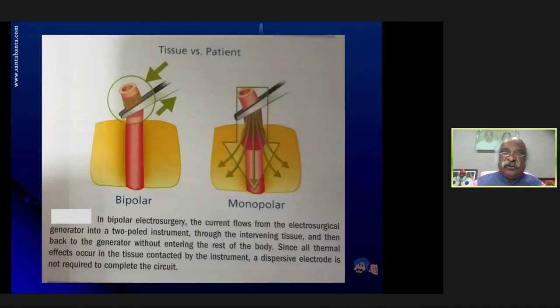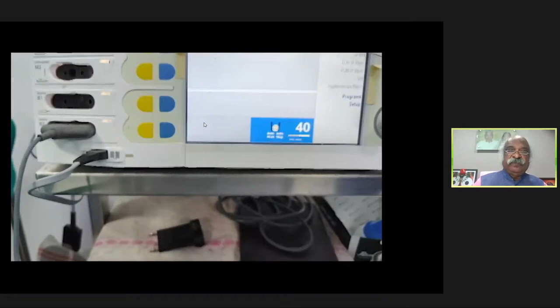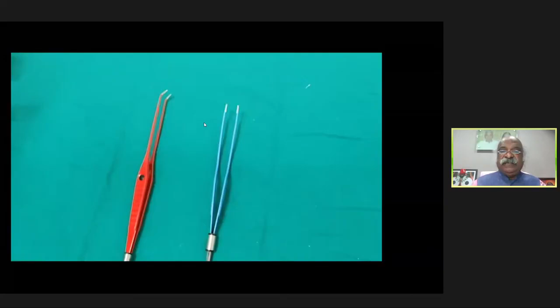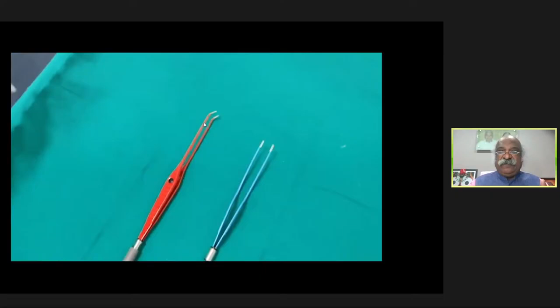Whereas in the monopolar, what happens? It goes through the electrode and directly through the tissues, and then it passes through the dispersive electrode and comes back. Now, you see what common things we use. These are all bipolar forceps. On the left side, I can find that there's a red forceps. The material is such that it doesn't stick.